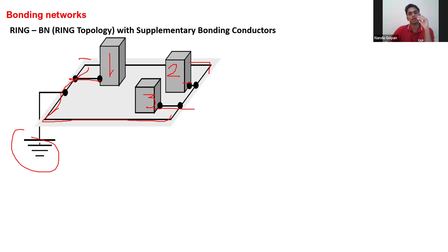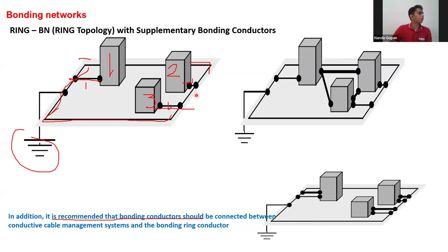Now, it is recommended to do additional bonding as well, because sometimes one connection here, one connection here, one connection here might not be enough. So it is recommended to make some additional connections here. It will reduce the resistance between this equipment and this line. Or you can also do interconnections in this type of view: equipment 1, 2, 3 interconnected in multiple places, which is also a very good system, much better than this one or this one. This is very efficient.